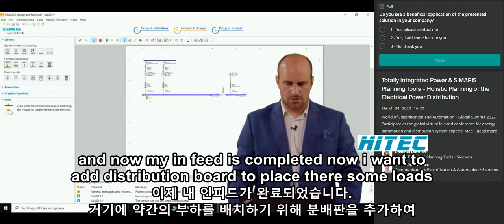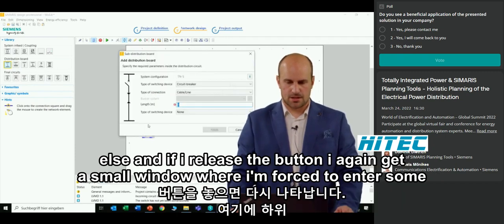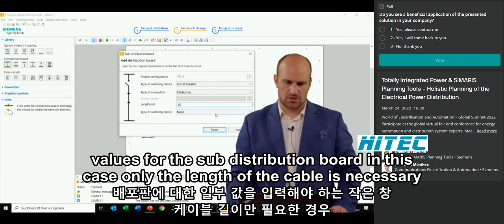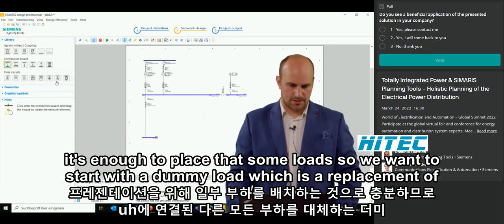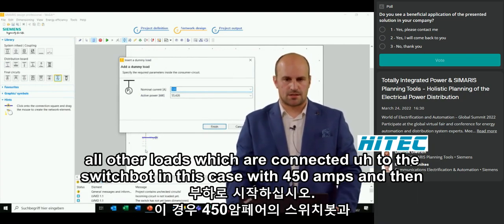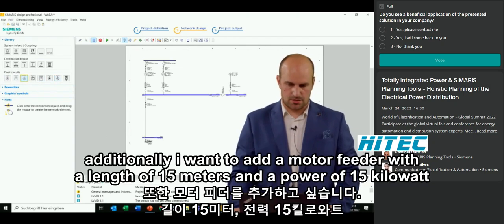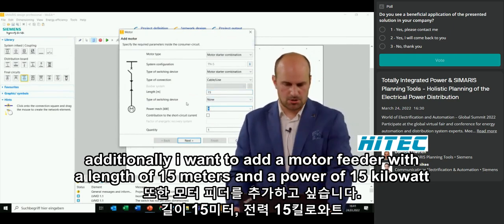Now I want to add a sub-distribution board to place some loads there. I wait until a yellow rectangle appears, move it, and release the button to get a window where I enter values for the sub-distribution board — only the cable length is necessary. I place it, and then add loads. We start with a dummy load — a replacement for all other loads connected to the switchboard — with 450 amps. Additionally, I add a motor feeder with a length of 15 meters and a power of 15 kilowatts.